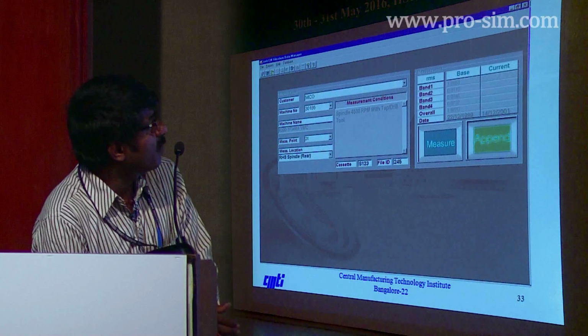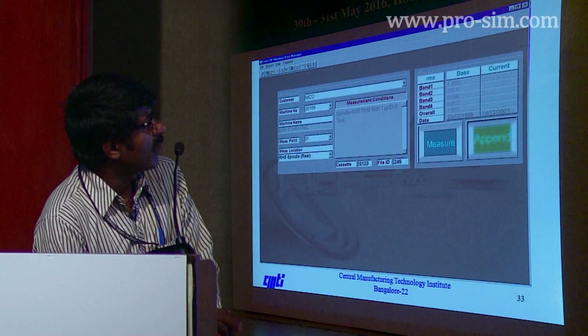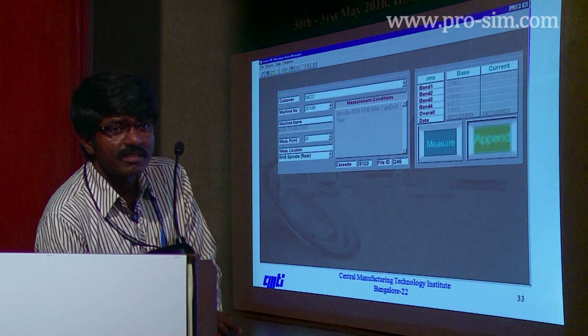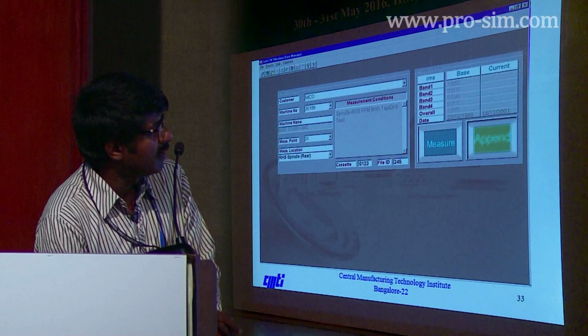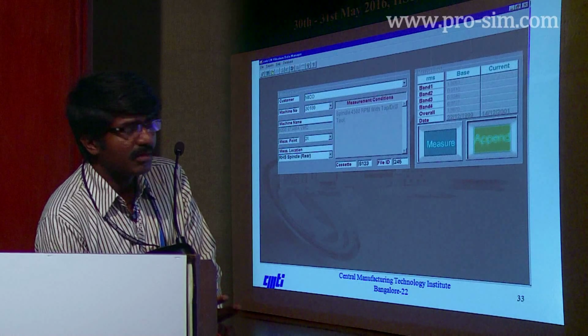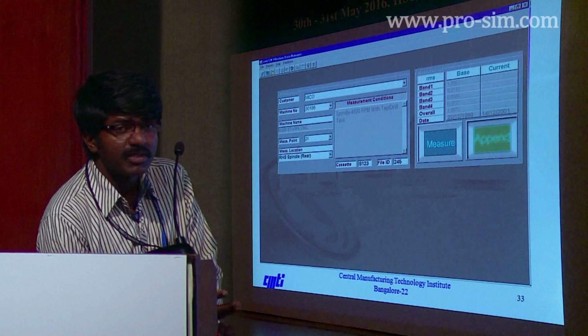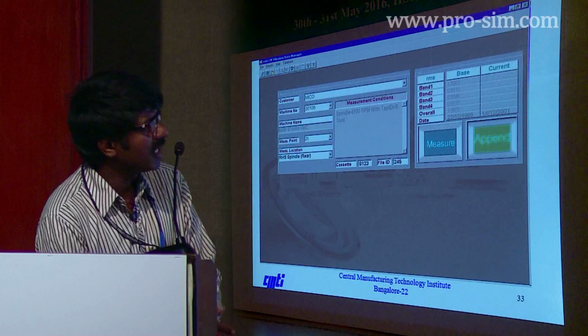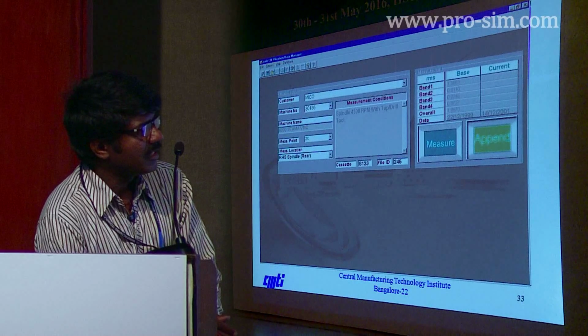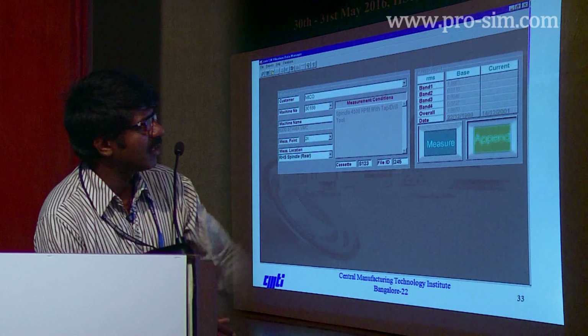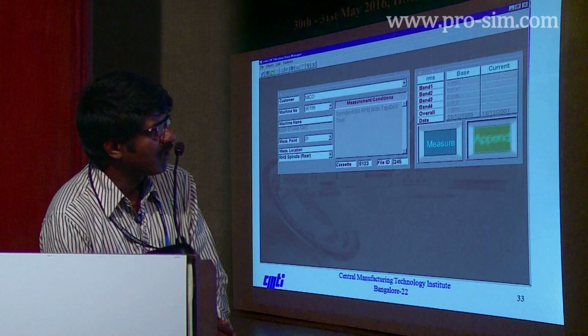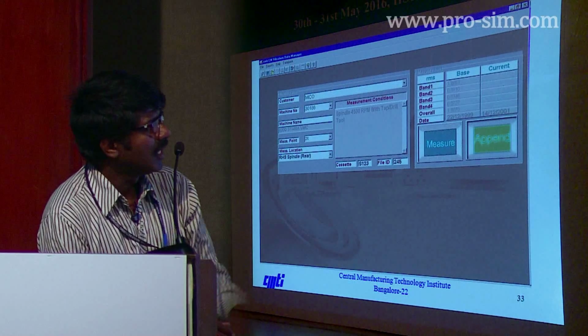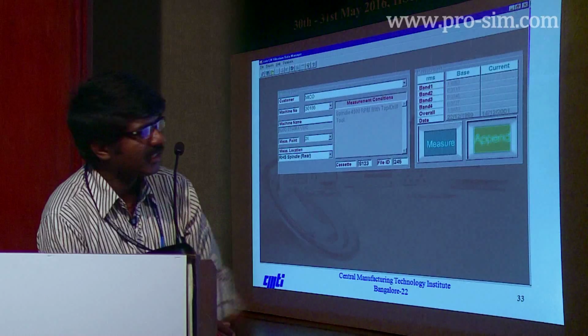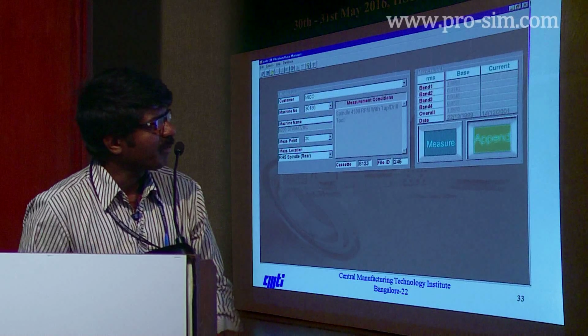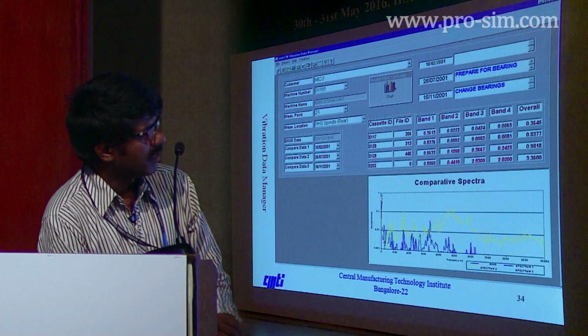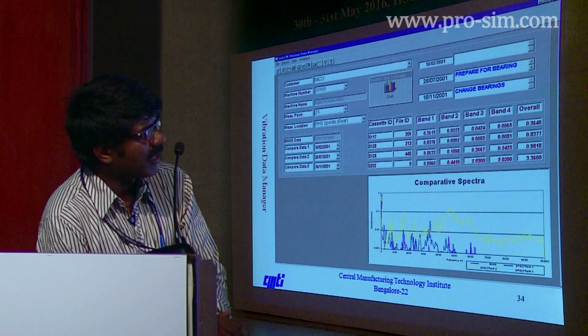So CMTI has developed this vibration data manager for data collection, analysis, and data management. In this you can select the machine number, the machine name, and the measurement locations. The moment you select, it will give you the base signature or the base vibration reading for that particular measurement location, and it will also give you the measurement conditions, under which condition you have to collect the data. Once you collect and append it, all the values get appended.